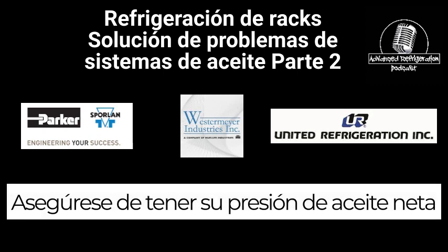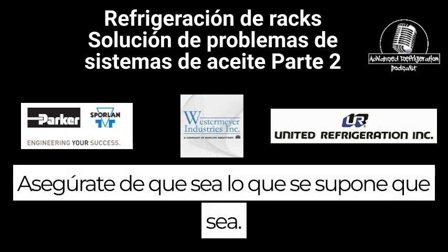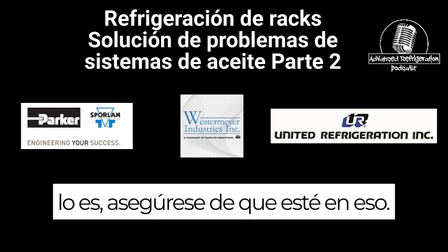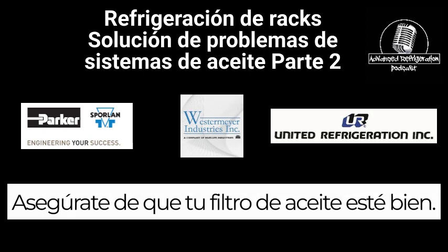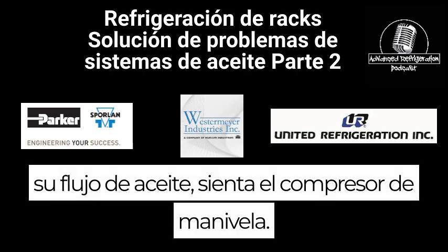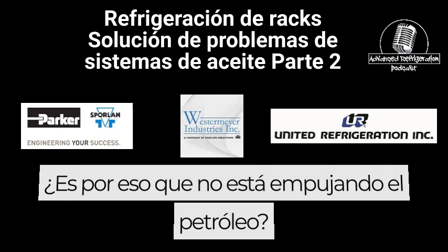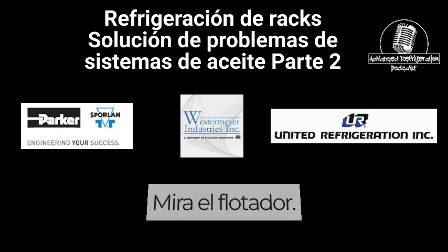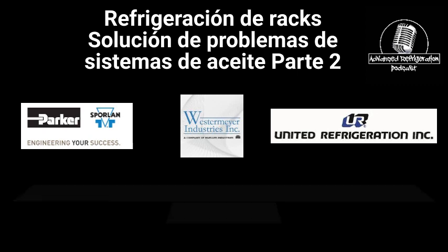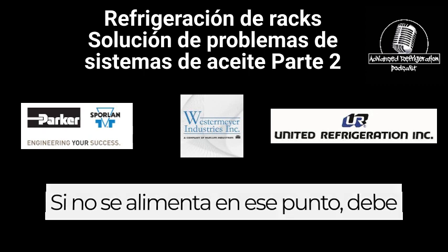Make sure you have your net oil pressure from your reservoir or your feed line to whatever it's supposed to be. If it's 20 pounds above suction, whatever it is, make sure it's at that. Make sure you have full flow. Make sure your oil filter's good. And then you want to look at your oil float. Feel the crank. Is the compressor smoking hot? Is it bleeding through? Is that why it's not pushing oil into the float? Look at the float. I would inspect this. I'll reset the float off the chart and see if it starts feeding oil, and see if it's set up to the chart properly.